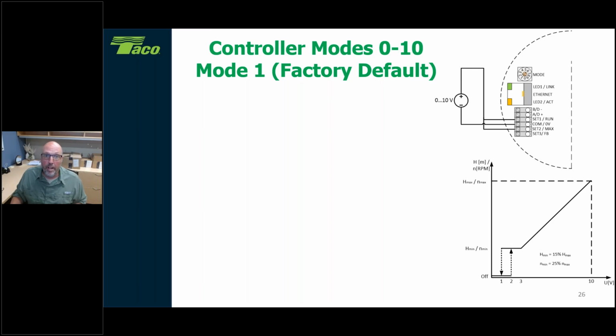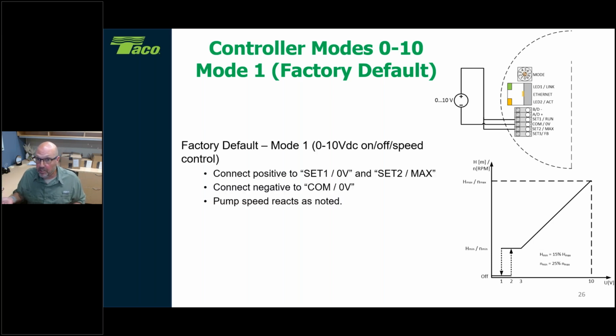So when you are in mode 1, like I said, this is the factory default mode. Here's your 0 to 10. Of course, that jumper cross comes off between set 1 and set 2. We put the 0 to 10 volt signal across the board here. And now the circulator will respond to that, speeding up and slowing down as you get that signal coming into the circulator itself.